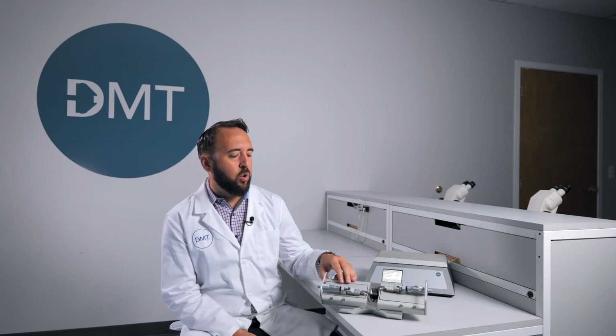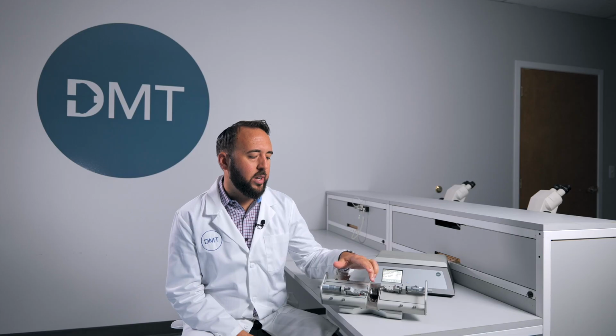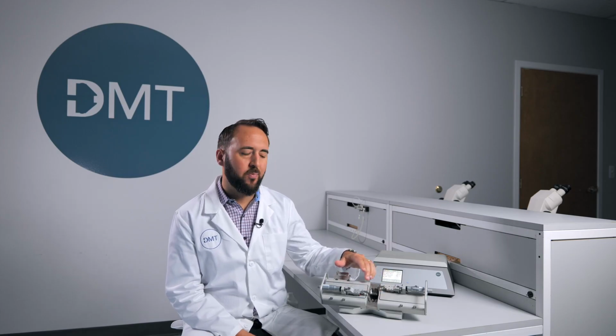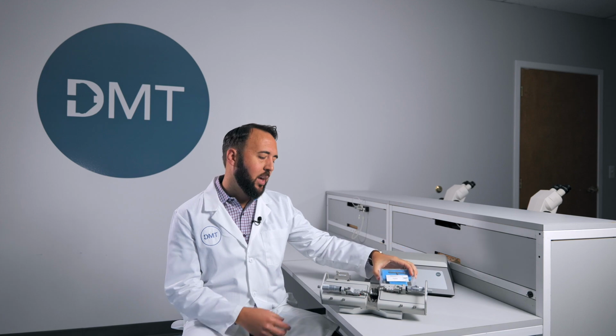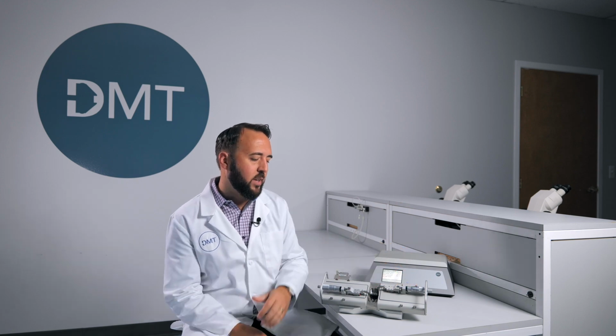to help the system. The calibrations are best done under experimental conditions, meaning you have the chamber warmed to 37 degrees Celsius or whatever your experimental temperature is, and you use the same volume in the chamber that you'll be using during the experiment. It's fine to use water for the calibrations. You can also do the calibrations at room temperature, but it's best done under experimental conditions. In order to perform the calibration, you will need a wire on each jaw that's attached to the force transducer, the calibration kit, and make sure that you have the myograph cable plugged in.